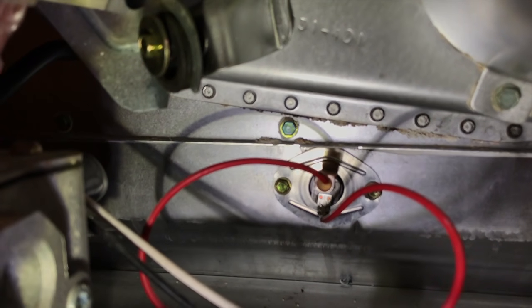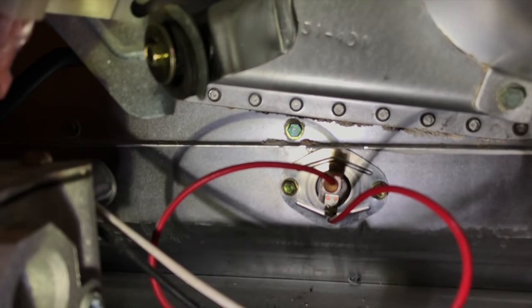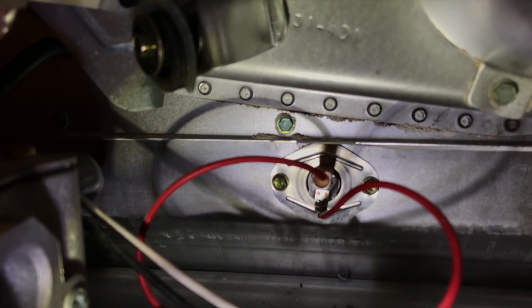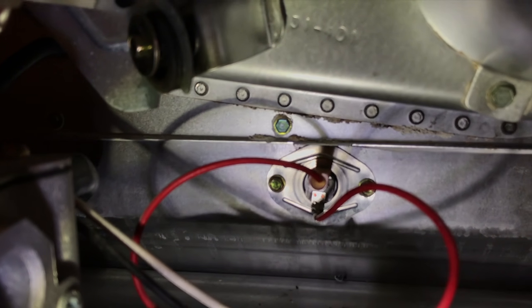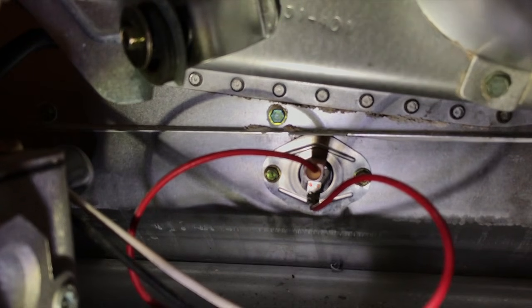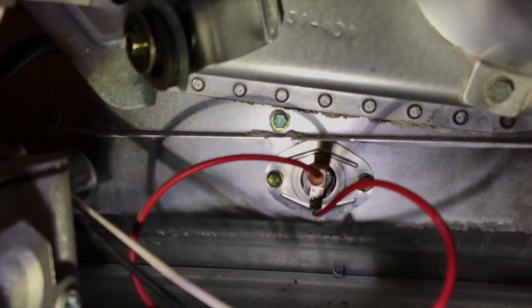The first thing it does is it does not allow the furnace to turn on until air inside your furnace is warm, and that's important. And that goes back to what we were just talking about with your air filter being clogged. And the second important thing it does is it acts as a kill switch to the burner if air temperature around the actual heat exchanger becomes too hot.